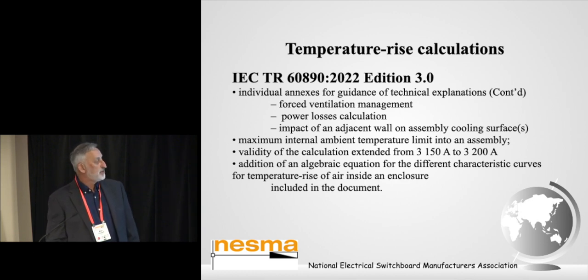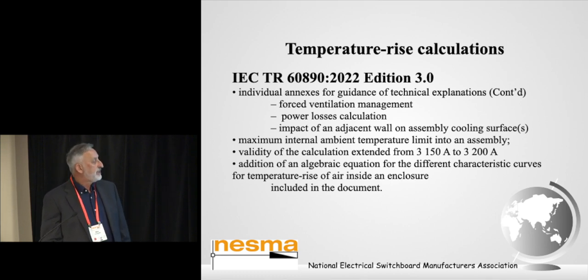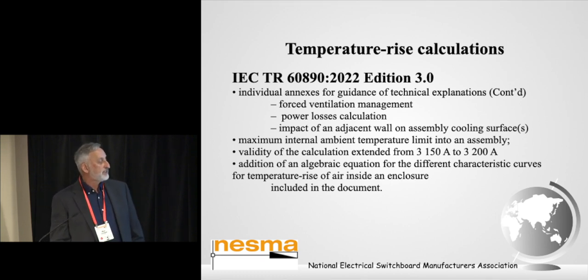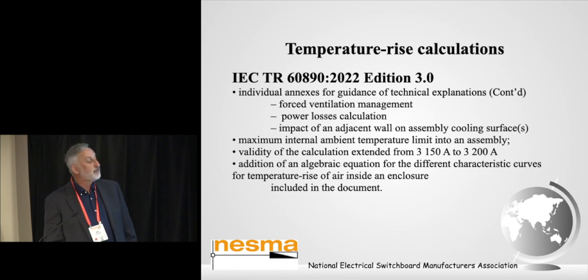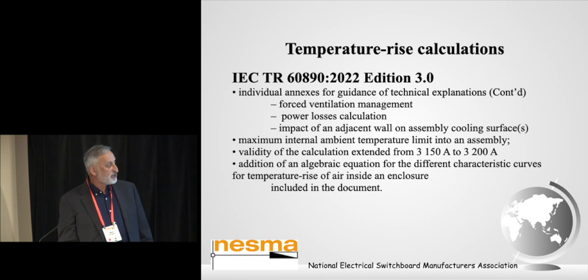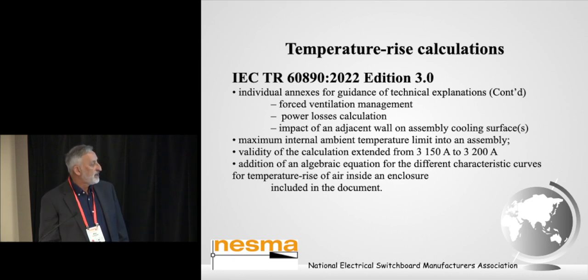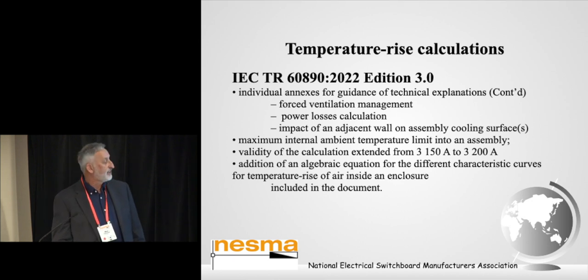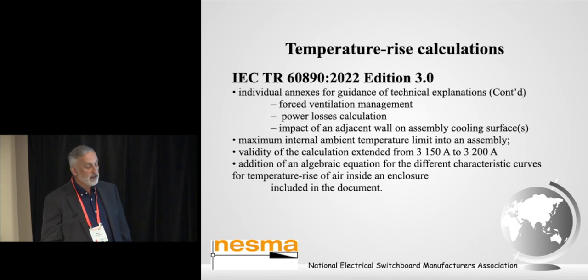It provides for maximum internal ambient temperature limit into an assembly. Validity of the calculations for such assemblies was extended to 3200 amps. And there's an addition of an algebraic equation for different characteristic curves for temperature rise of air inside an enclosure included in the document, rather than just doing it off some curves.